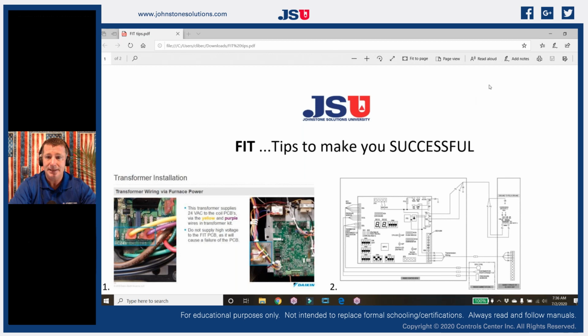So if we look at this particular wiring diagram here, I'm going to grab my highlighter. So here on the right hand side, this board is the actual layout of the control board that is on that electronic expansion valve air handler. This happens to be the cased coil version. So on that control board, coming from our air handler or gas furnace, we are going to add an additional transformer. So they send a transformer with that so we can supply an additional power source for this control board. So at our indoor unit, we're going to install a new transformer, and it is there only to feed 24 volts to TR1 and TR2 or TH2. So that is our 24 volt power supply that feeds this entire coil or control board.